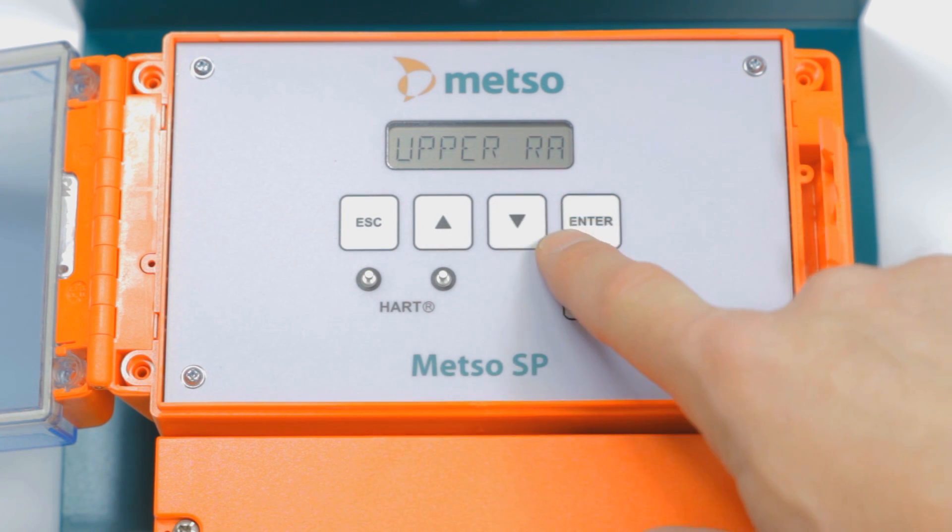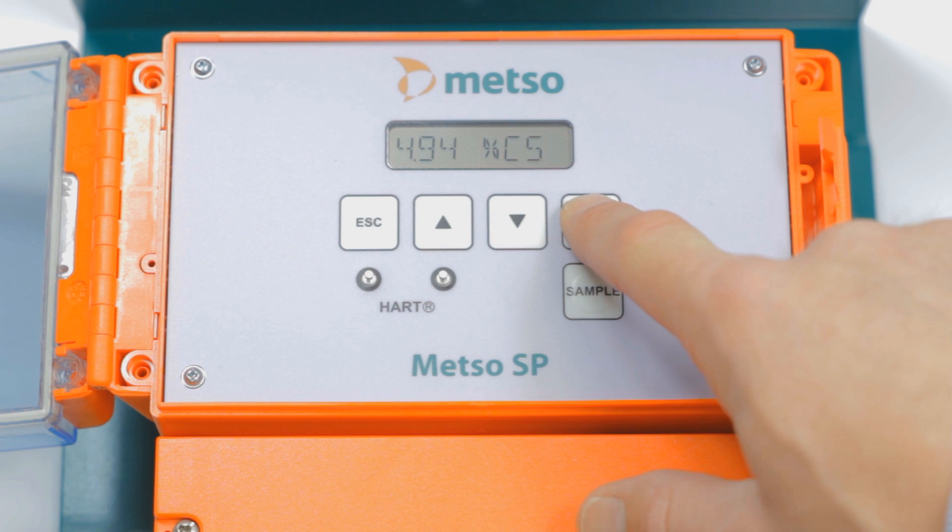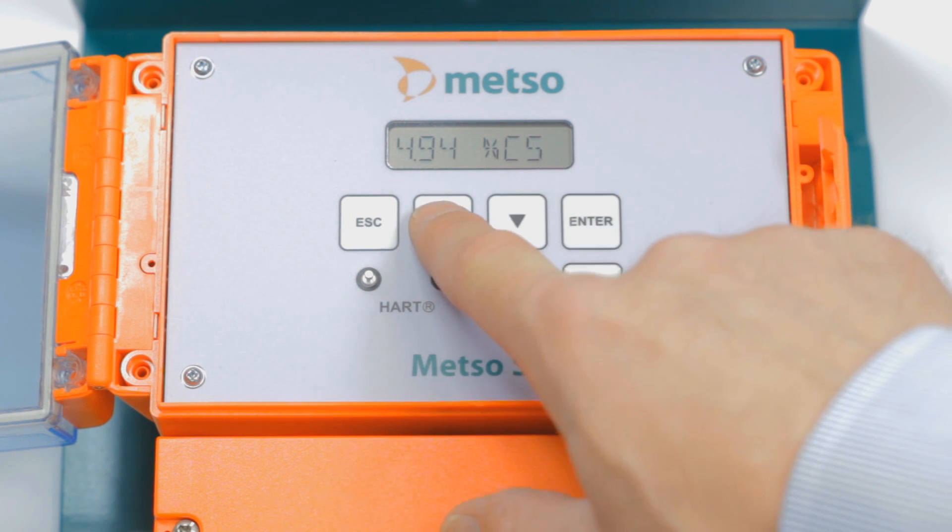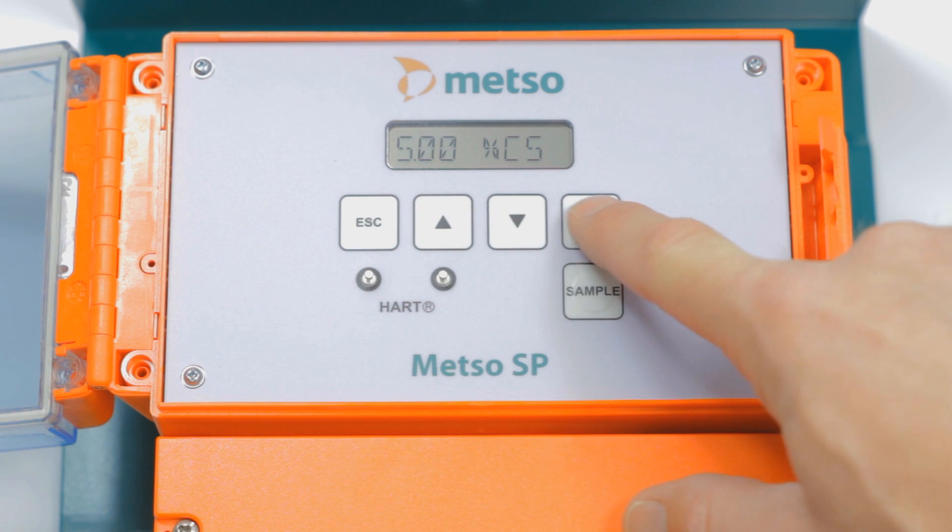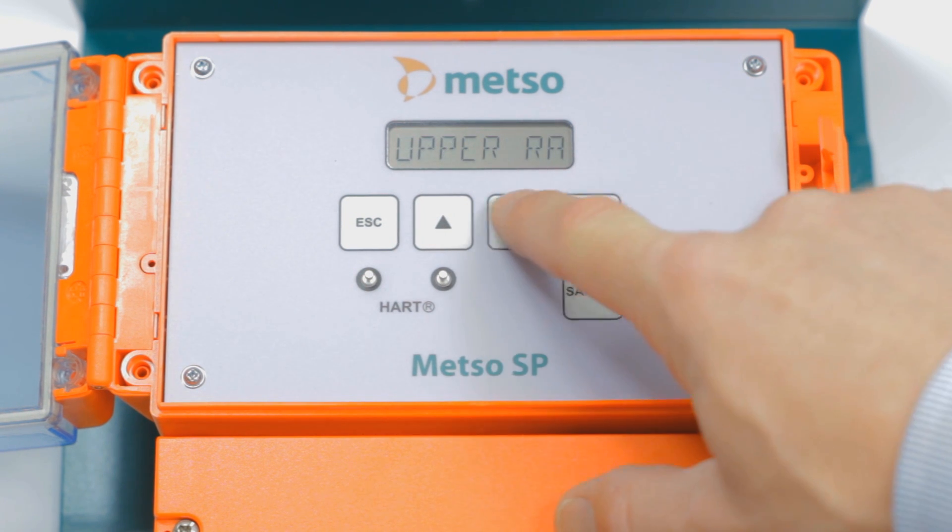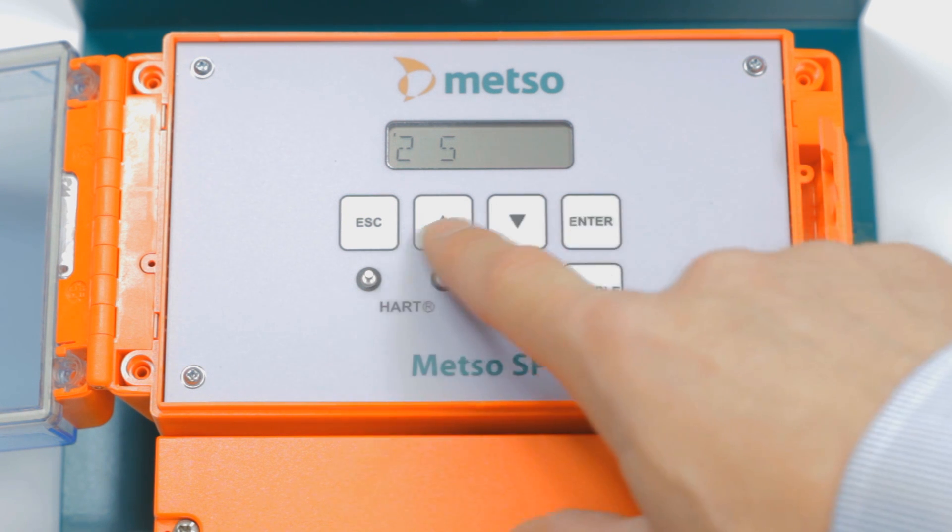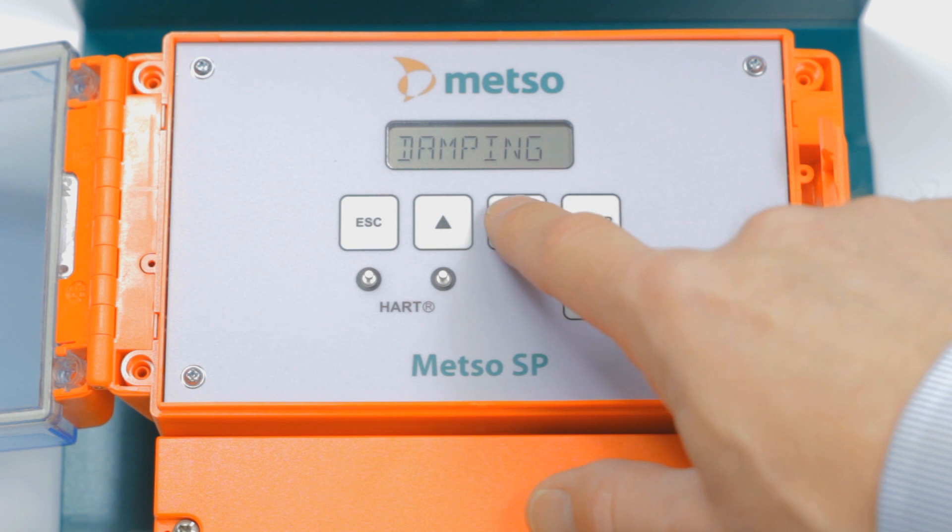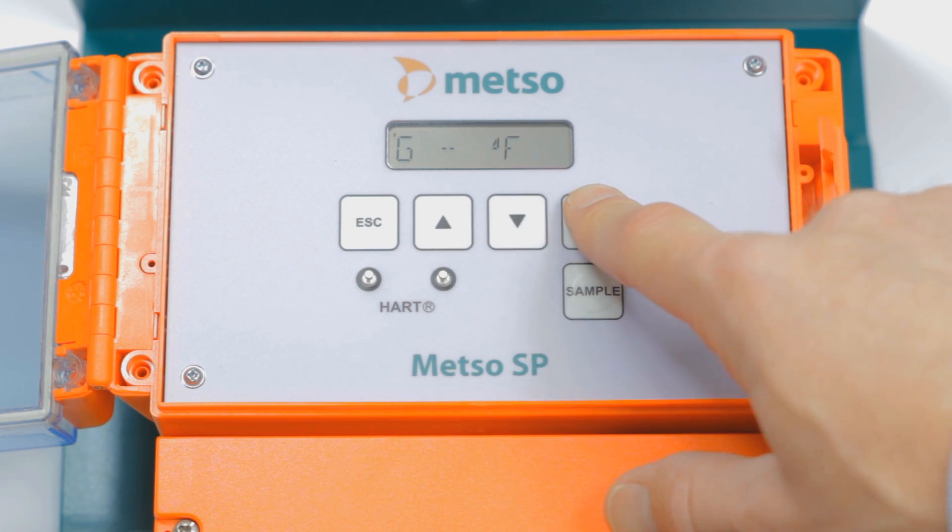And then we're going to arrow down to the upper range. And we want that at 5.00, so we're going to bring that up and hit enter and accept that. We can arrow down. Dampening, default is 2 seconds. We can enter to accept it. Language, English, units, grams, and Fahrenheit. We're going to accept that.